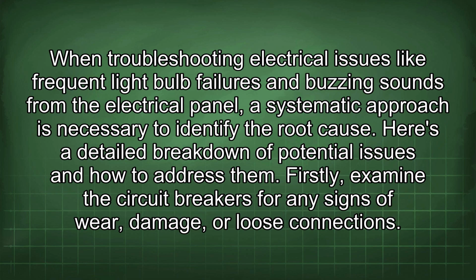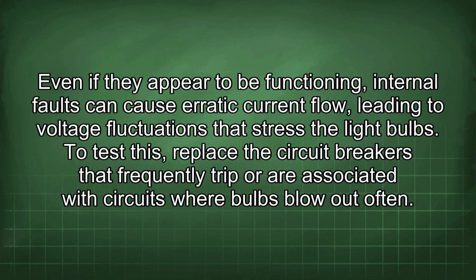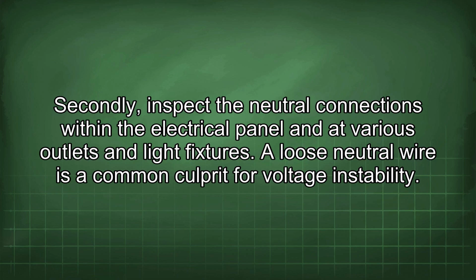Firstly, examine the circuit breakers for any signs of wear, damage, or loose connections. Even if they appear to be functioning, internal faults can cause erratic current flow, leading to voltage fluctuations that stress the light bulbs. To test this, replace the circuit breakers that frequently trip or are associated with circuits where bulbs blow out often.